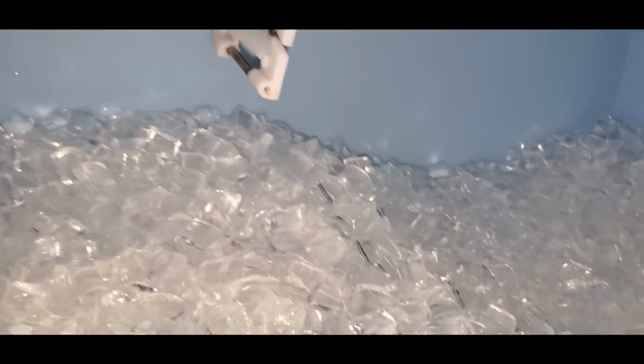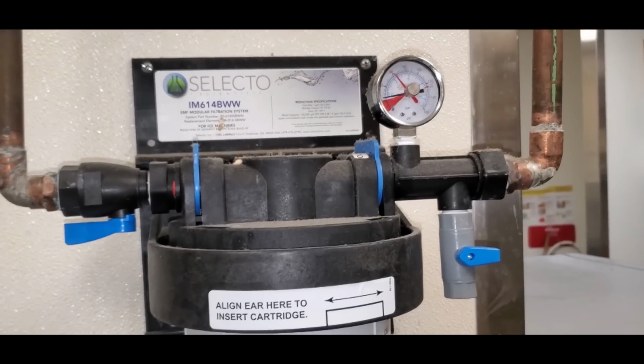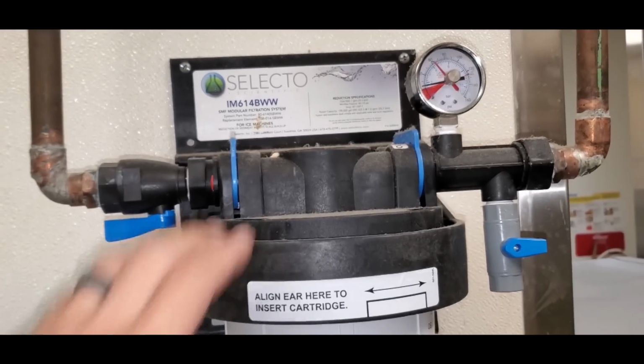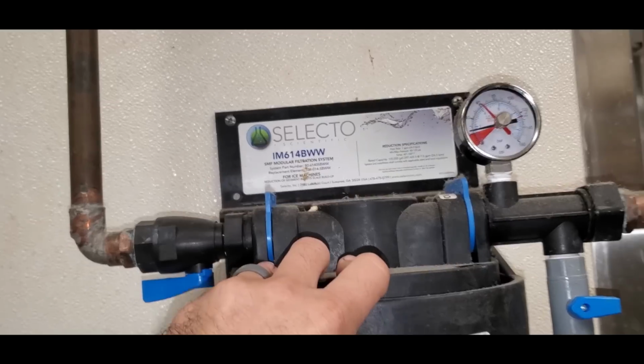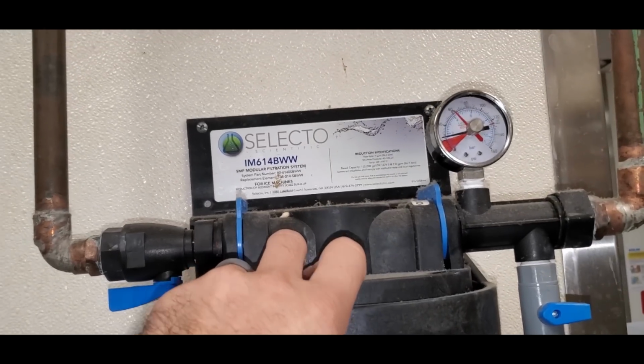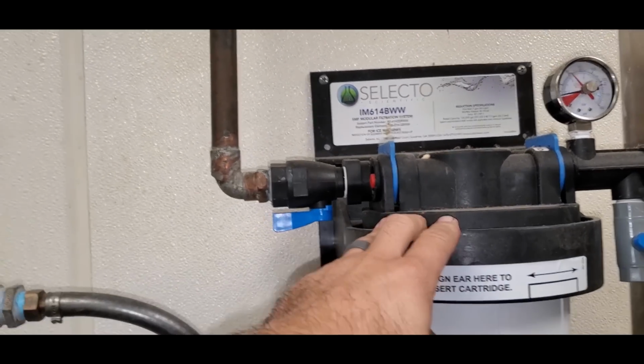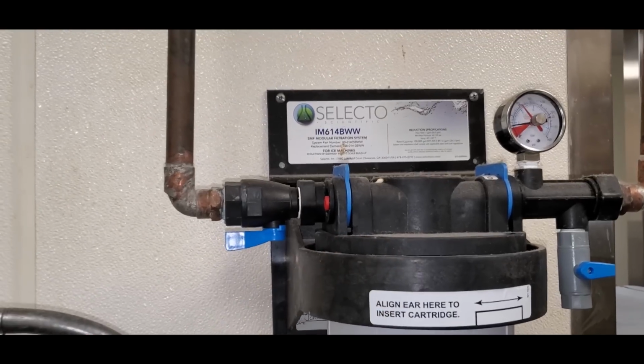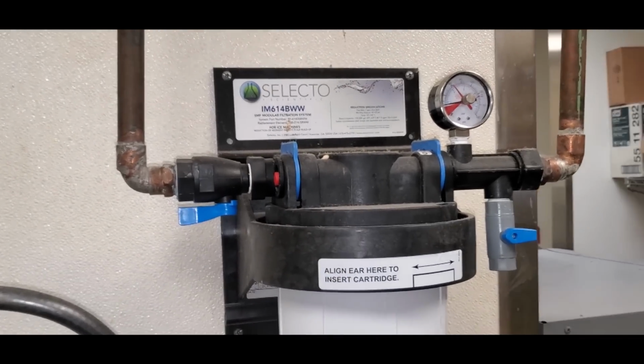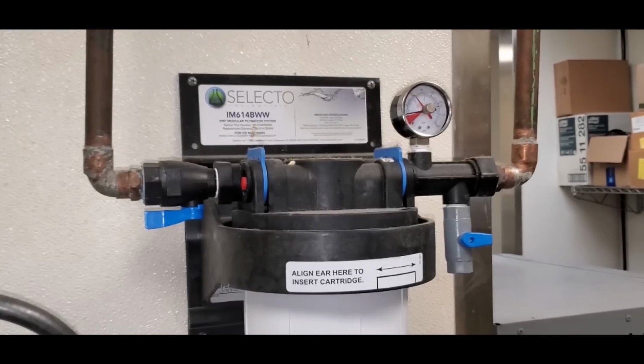So it's working, which is interesting, but it's peculiar that it's full of ice. We do have very low water pressure, though not horrible - about 20 psi - but I still don't like how low that is. These are the difficult things when a unit's been reset; we run into these problems and have to try to guess.